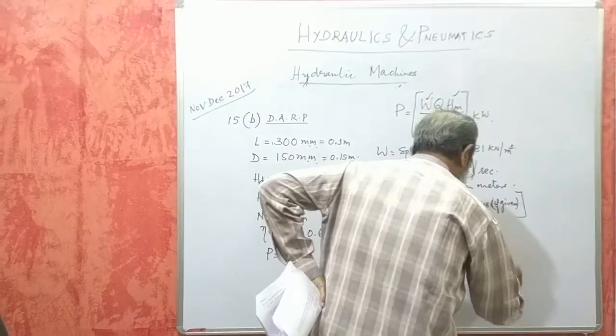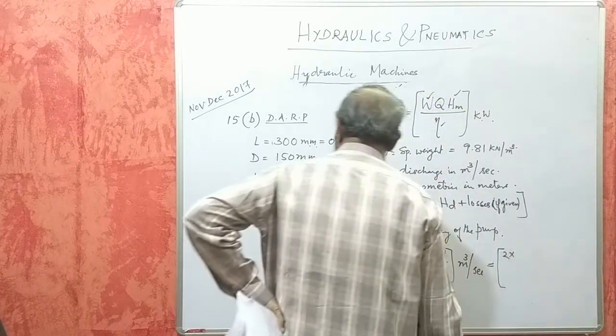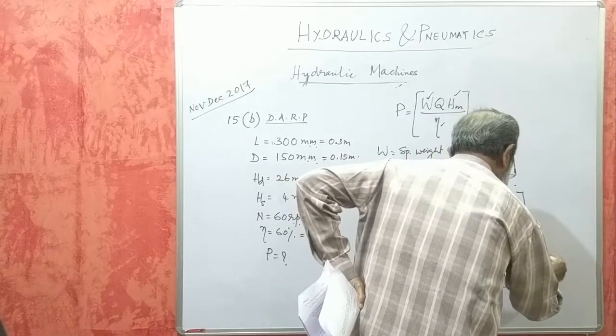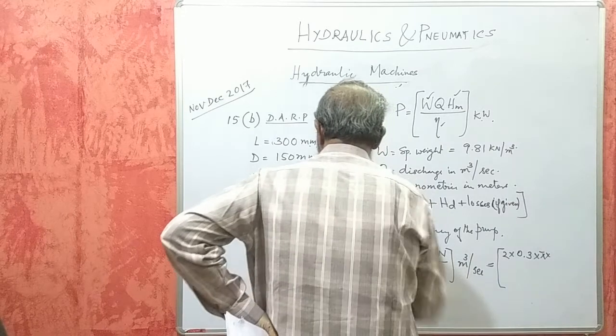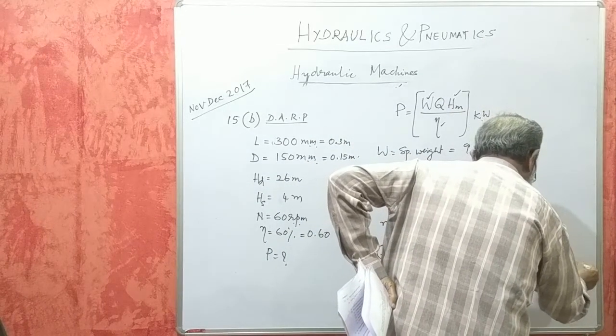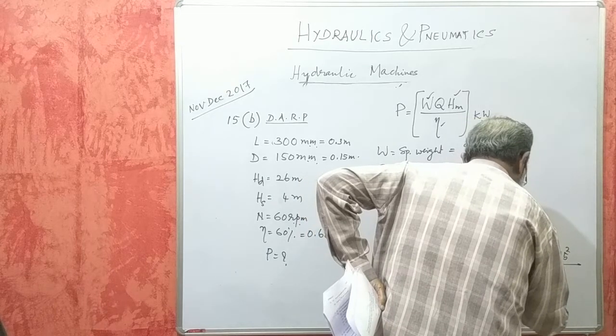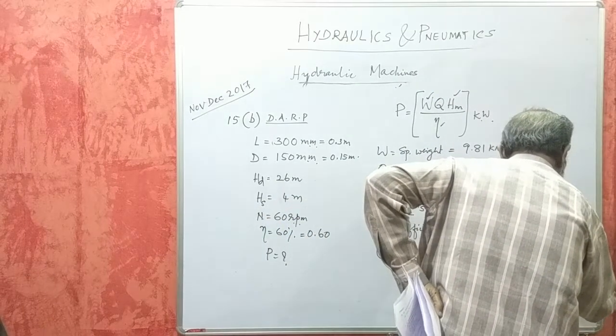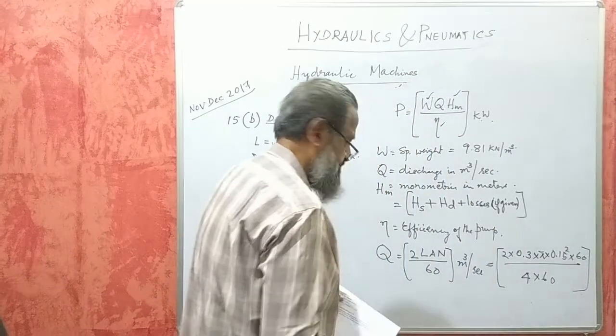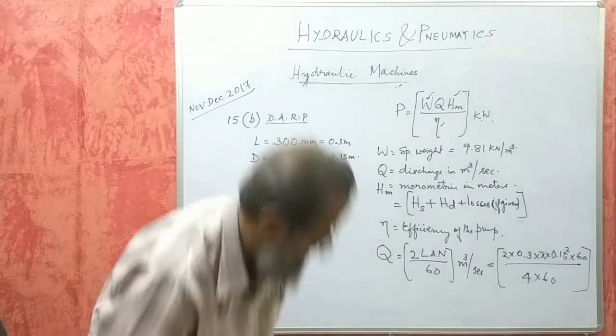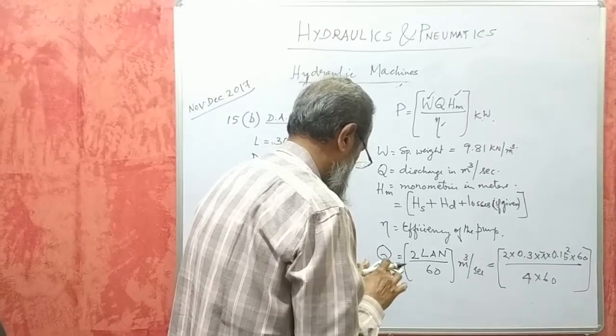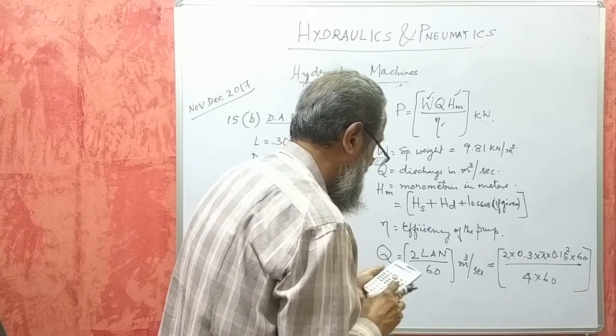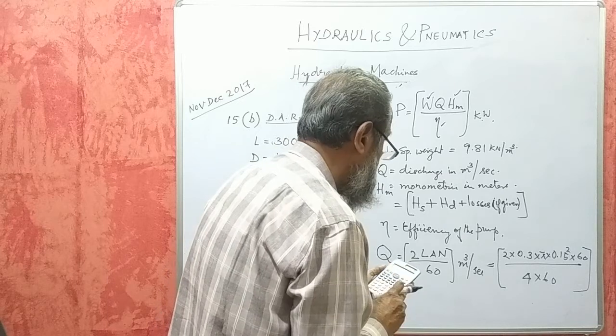L is the stroke length, substituted in meters — it is given as 300 mm, converted to 0.3 m. A is the area of the cylinder: π·D²/4, where D is 0.15 m, so A = π × (0.15)² / 4. N is 60 RPM. So Q = 2 × 0.3 × π × (0.15)² / 4 × 60 / 60.